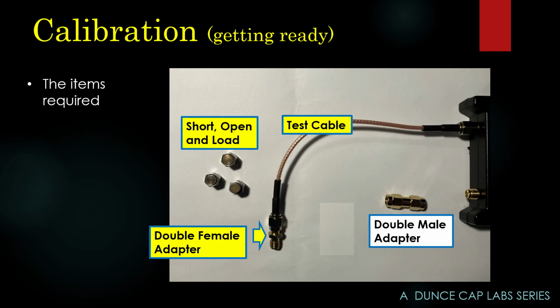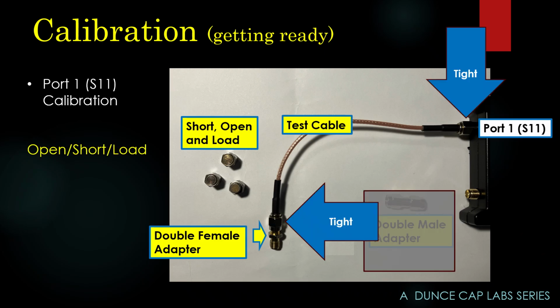First, you're going to do the regular calibration with the items in yellow, and then you're going to grab the double male adapter and do the 2nd port calibration. If I don't say it often enough, and I'm sure I don't, make sure connectors are tight. The 2 in blue you can permanently tighten. The ones at the double female adapter you can use wrenches. The one at port 1, I use a small pair of pliers. I don't get too carried away with it, but I do keep it good and tight.